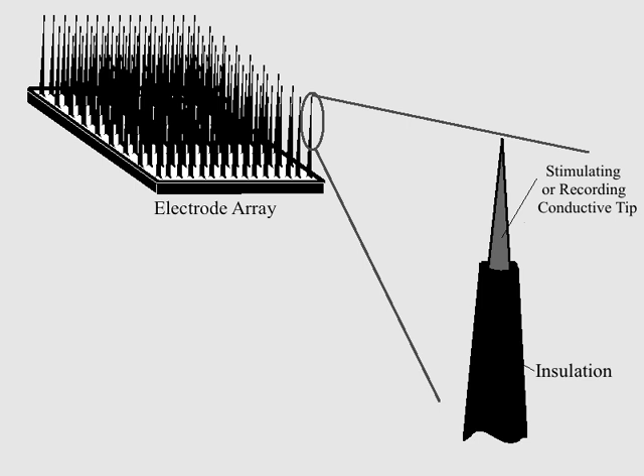Electrodes, especially stimulating electrodes and the high current density they discharge, can raise electrochemical issues. Electrodes will be surrounded by tissue and electrolytes; stimulation, resultant electric fields, and induced polarizations will change local ion concentrations and local pH, which can then cause problems such as material corrosion and electrode fouling. Pourbaix diagrams show the phases that a material will take in an aqueous environment, based on electrical potential and pH.